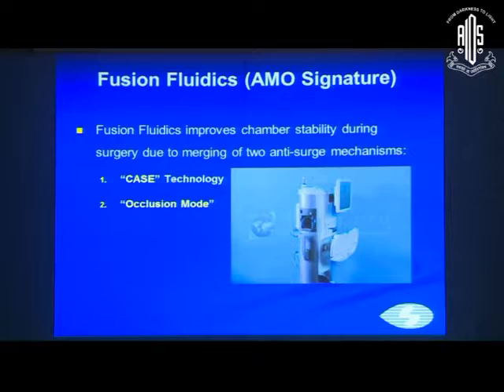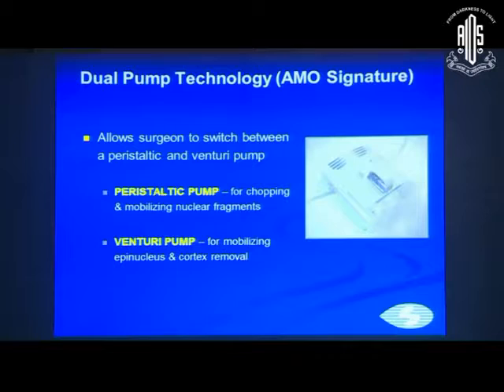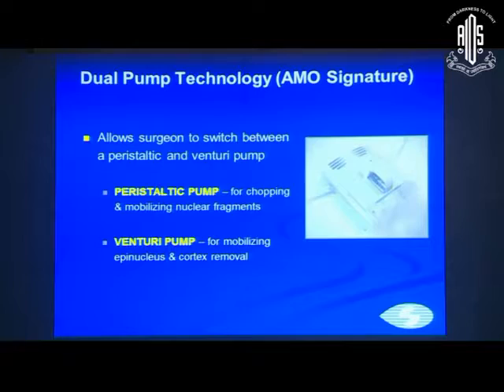Fusion Fluidics in AMO combines both CASE technology and occlusion mode technology, which work together as anti-surge mechanisms. It also features dual pump technology combining the peristaltic pump and the venturi pump — peristaltic is good for chopping and mobilizing fragments, while venturi is good for epinucleus and cortex removal.